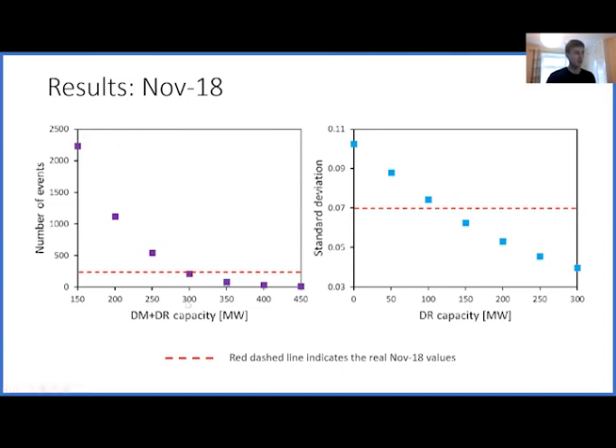If their sum is 300 megawatts, you get a similar number of events to what really happened in November 2018. I found that the only thing that really affected the standard deviation was the dynamic regulation capacity. Dynamic regulation, to remind you, is the one performed continuously with very tight regions of when it's used. Somewhere between 100 and 150 megawatts of this is enough to bring the standard deviation to what was seen in November 2018.